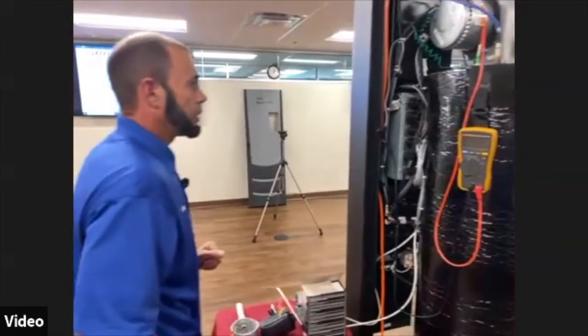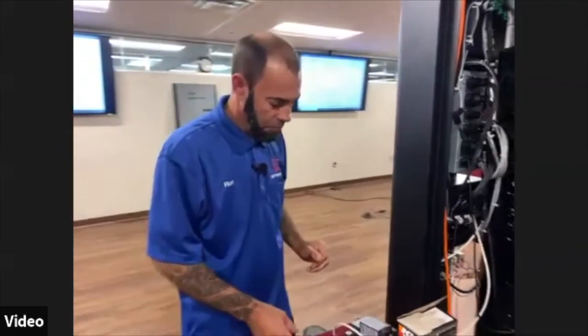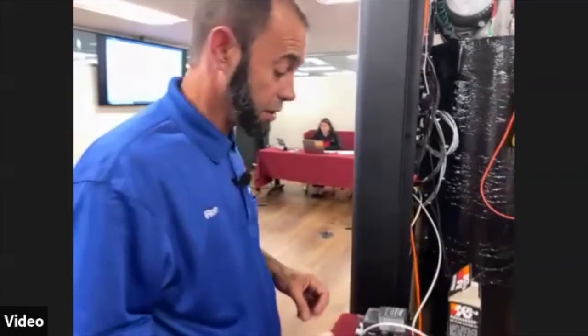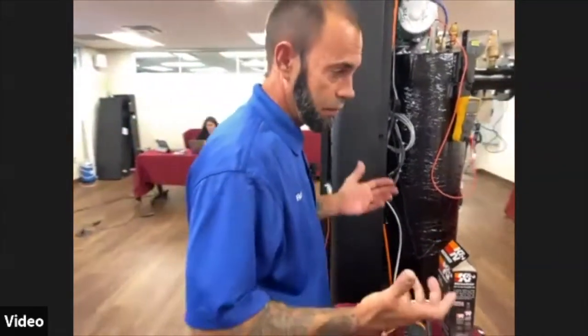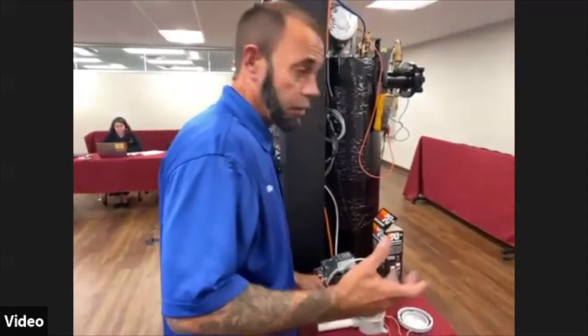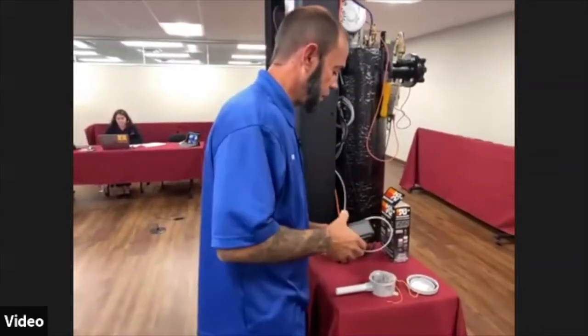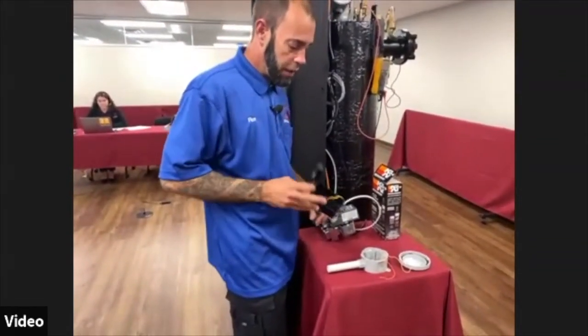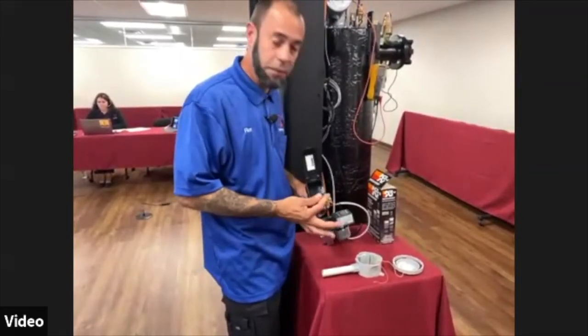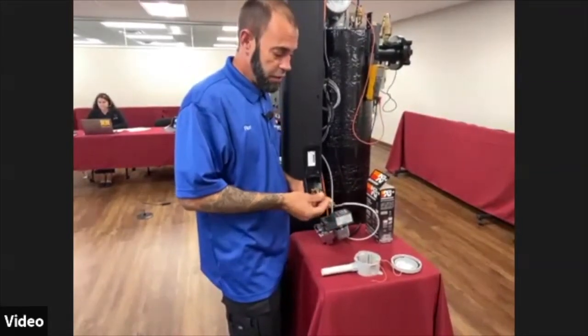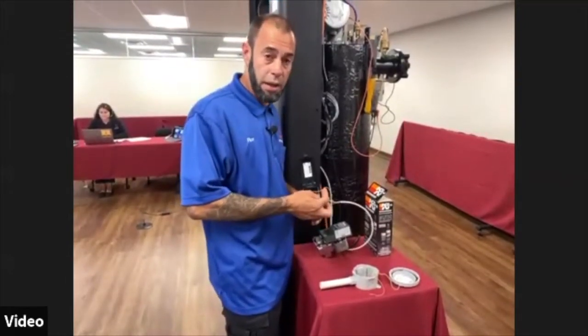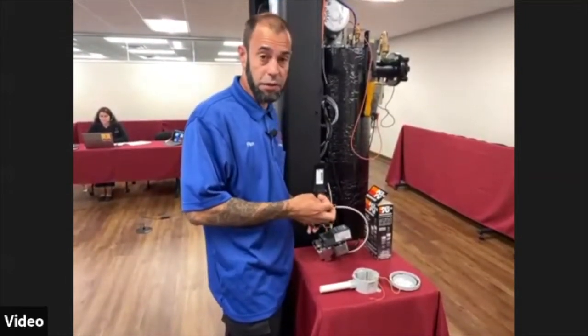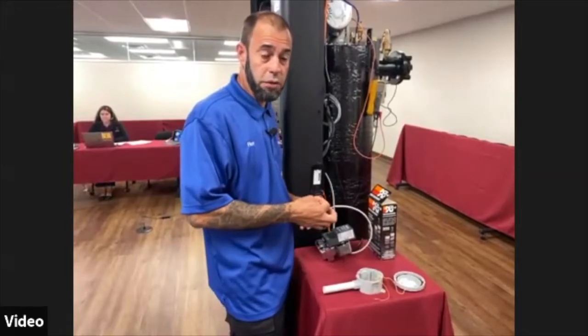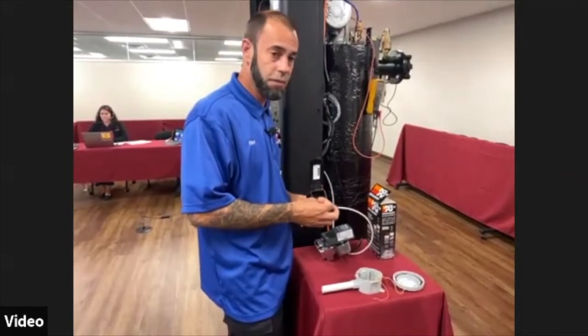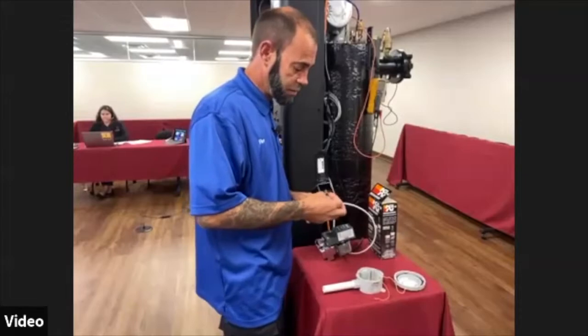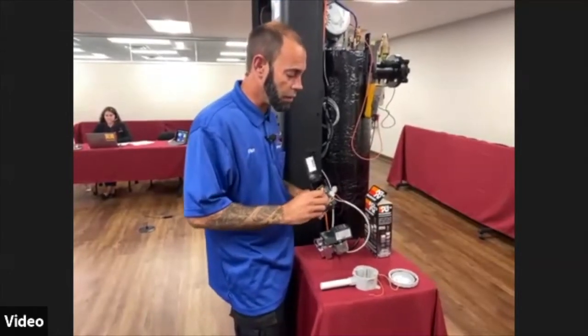As we come around the other side of the boiler, again, because we have set this up in BST, and we've basically made it a manager for testing purposes today, we've wired in the header sensor just temporarily. The header sensor is a 1 k ohm at 70 degrees Fahrenheit, and it's 2.2 ohms of resistance for every degree above that or below that, I believe it is as well.